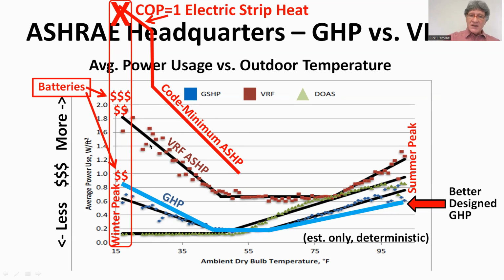But the comparison here is that this was an ASHRAE study, where they took floors in a particular building and built one out with VRF, one with higher grade VRF, and one with lower grade GHP geothermal. The VRF, even the high grade stuff, cost more than double to run for the year. And this system wasn't even designed well—this loop was out of balance. We could get into that another time. This can even be done better than this.